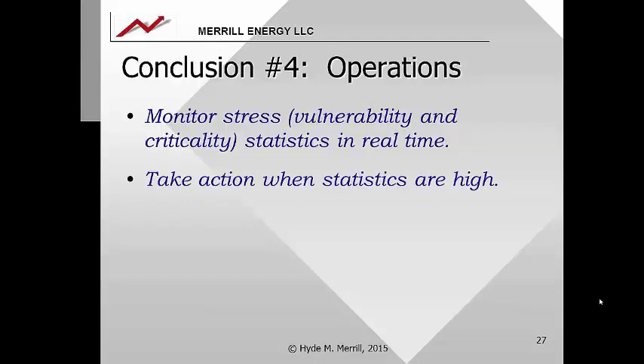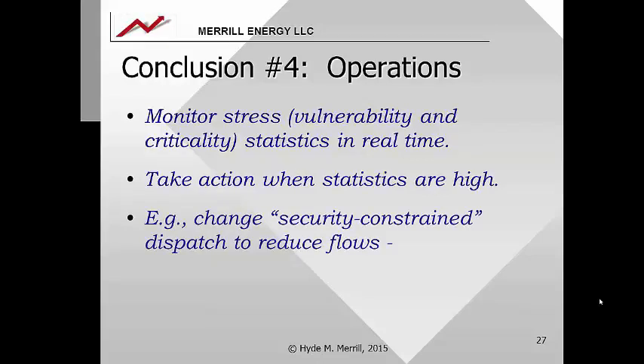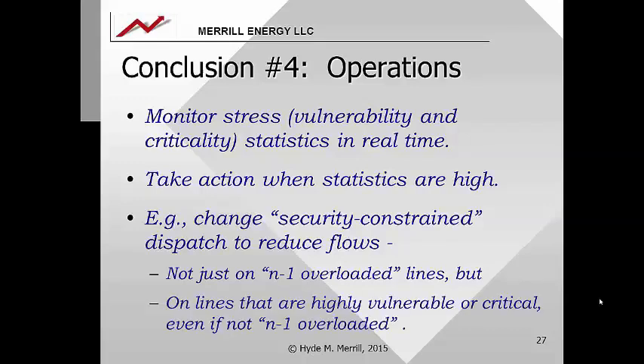Right now there's a function called security constrained dispatch, used so that in an N-1 situation - if a single contingency would cause a line to overload - the system is redispatched so that line wouldn't overload on that contingency. Well, that needs to change. We shouldn't just respond to N-1 overloaded lines, but should respond to lines that are highly vulnerable or critical, even if they're not N-1 overloaded.